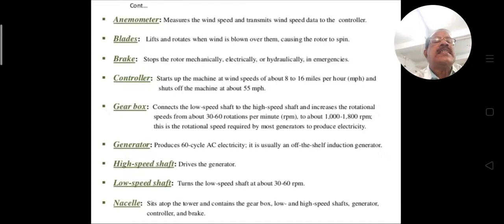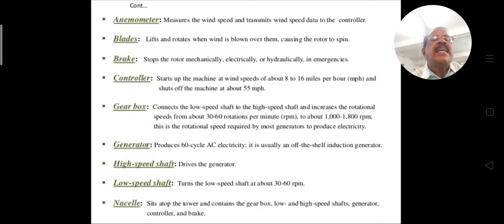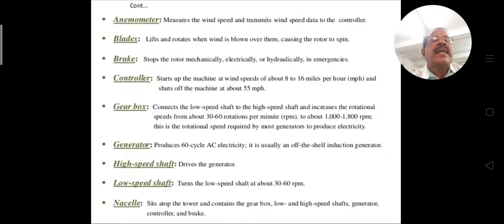The generator produces 60-cycle AC electricity and is usually an induction generator. It converts wind energy into electric energy. The high speed shaft drives the generator. The low speed shaft turns at about half to one rotation per second, that is, 30 to 60 rotations per minute.